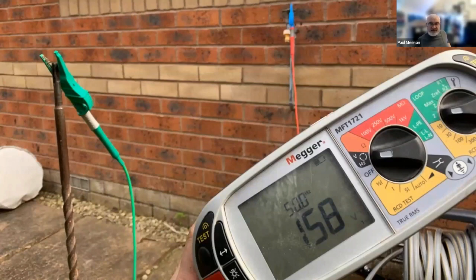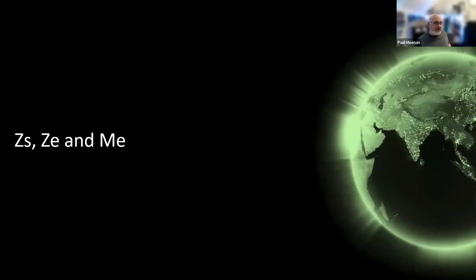It was taken at a domestic property, and that just shows you a broken neutral on the supply, 158 volts, and the clip is attached to the outside water tap, which people plug their hose in. And then the electrician just put a drill into the ground and measured 158 volts. So that just proves the concept of voltages grading across the ground. They can be a hazard because I could touch that drill bit and also the tap and get an electric shock. So just be careful when you are configuring your earthing and bonding.